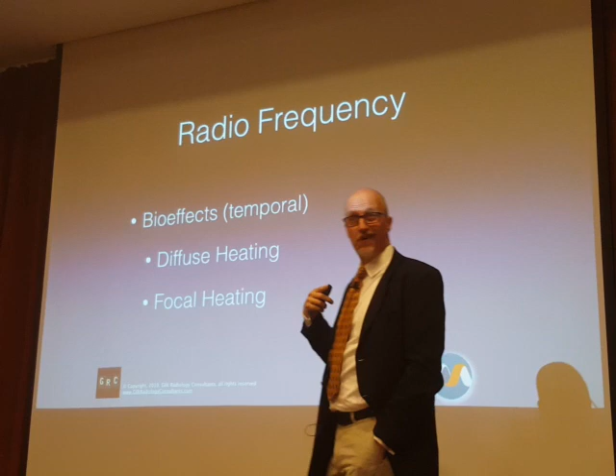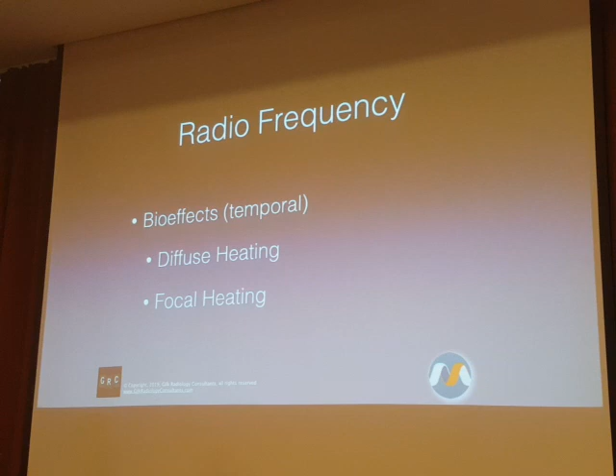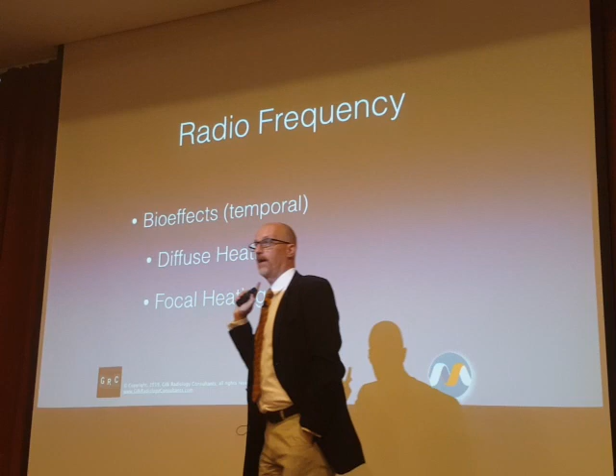And this heating can be produced in two ways: diffuse warming or focal heating or burns. As with both static field and time-varying gradients, to the best of our knowledge, radio frequency bioeffects are fairly benign. There are some people who contend otherwise. There are not large-scale reproducible studies that indicate long-term biological effects from radio frequency exposure. But this is not as settled as static field or time varying.